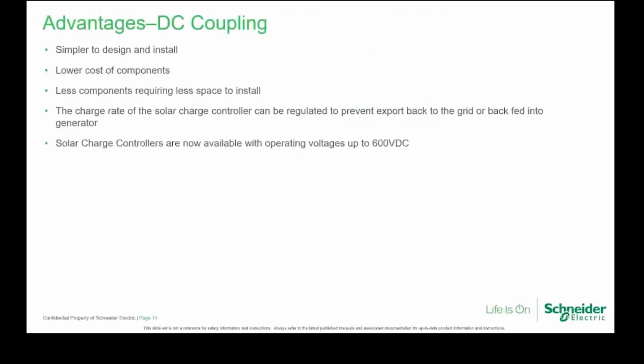So the advantages of DC coupling: basically, it's simpler to design and install. It has lower cost of components, less components required, so less space to install. The charge from the solar charge controller can be regulated to prevent export back to the grid or back feed into the generator, which means the XW actually regulates how the energy is being used and then directs it accordingly. And also solar charge controllers are now available with operating voltage up to 600 volts DC, which makes them equivalent to a grid-tied inverter.